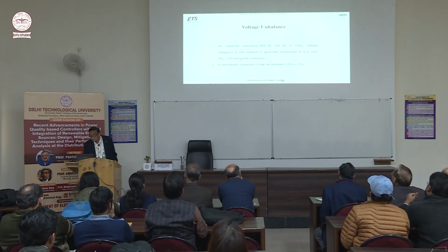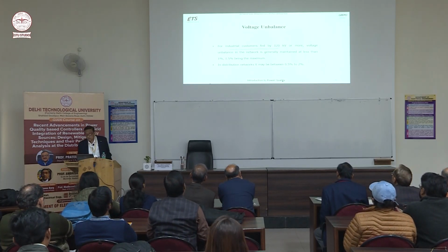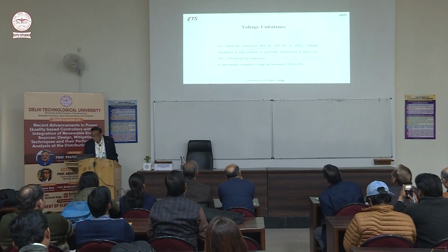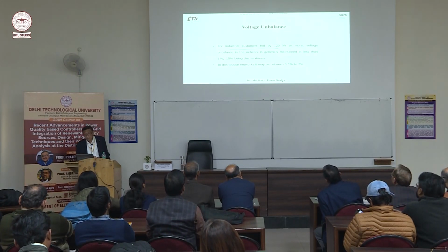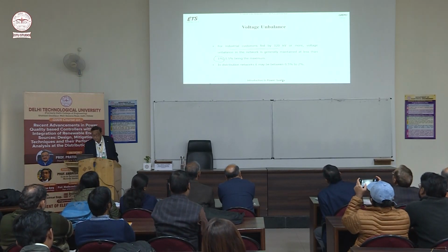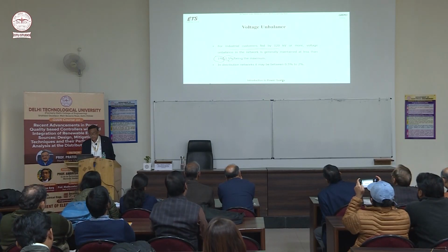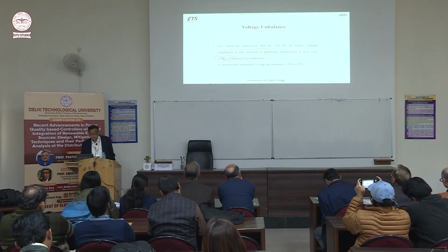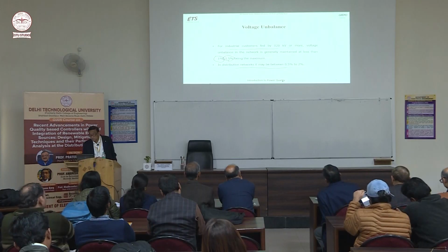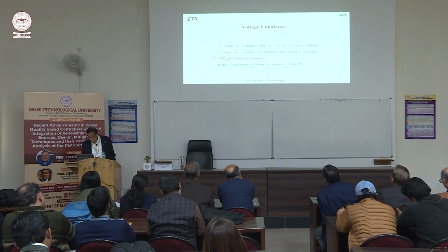For industrial customers fed by 120 kV or more, voltage unbalance in the network is generally maintained at less than 1%, or maximum 1.5% of voltage unbalance. In a distribution network, it may be between 0.5 to 2%.